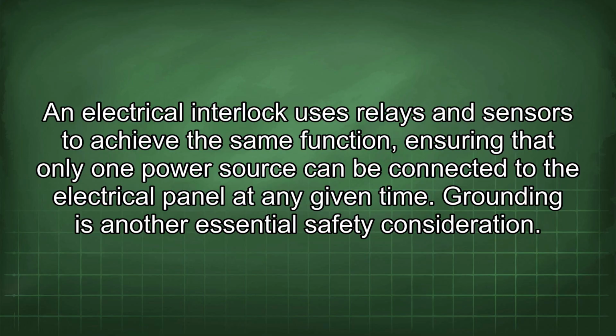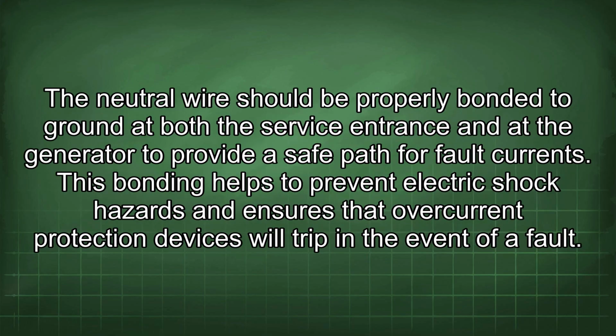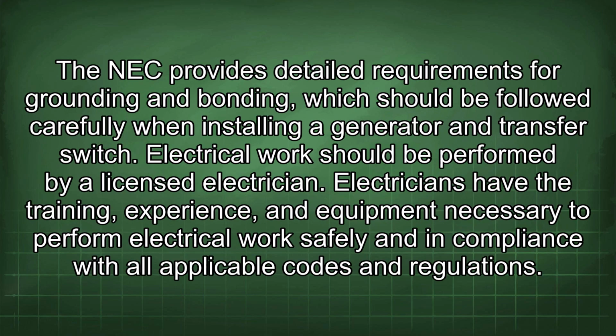Grounding is another essential safety consideration. The neutral wire should be properly bonded to ground at both the service entrance and at the generator to provide a safe path for fault currents. This bonding helps to prevent electric shock hazards and ensures that overcurrent protection devices will trip in the event of a fault. The NEC provides detailed requirements for grounding and bonding, which should be followed carefully when installing a generator and transfer switch. The electrical work should be performed by a licensed electrician.